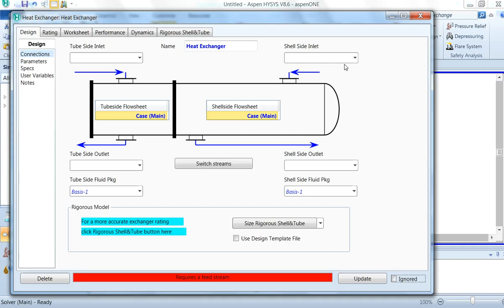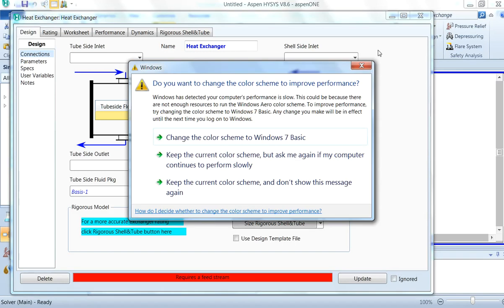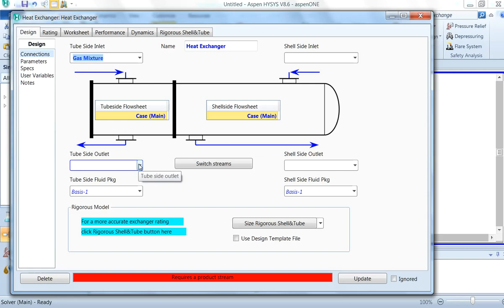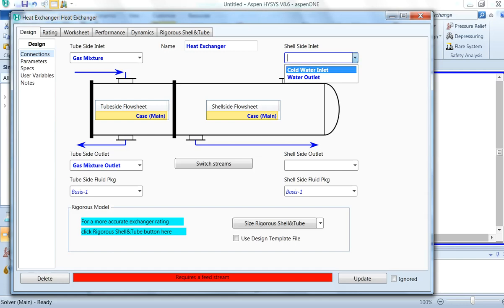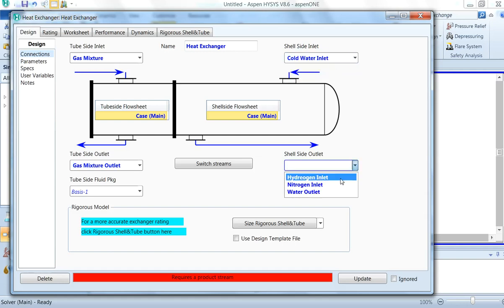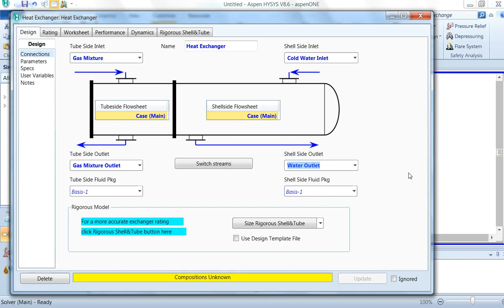In short, tube side fluids are: corrosive fluids, cooling water, fouling fluids, less viscous fluids, high-pressure streams, and hotter fluids. Shell side fluids include condensing vapor, unless it is corrosive, or fluids with a large temperature difference (greater than ~40°C). Naturally, the gas mixture is the hot stream — so the tube side inlet is the gas mixture and tube side outlet is the gas mixture outlet. Shell side fluid will be cold water inlet, and shell side outlet will be water outlet.